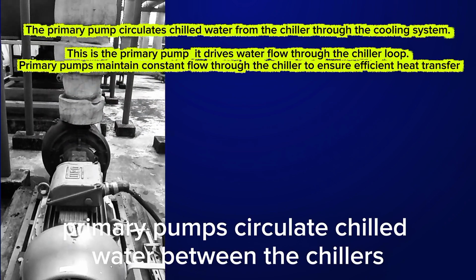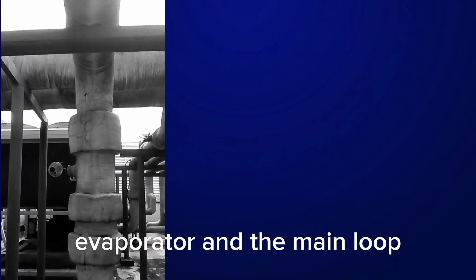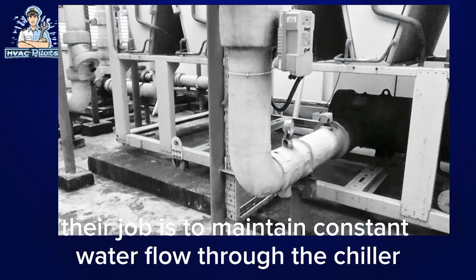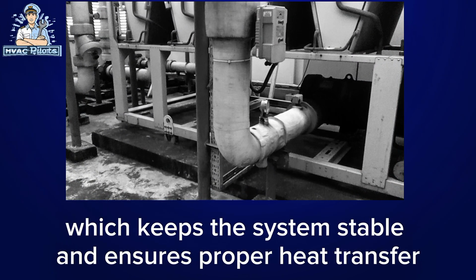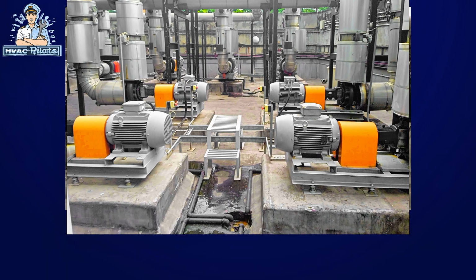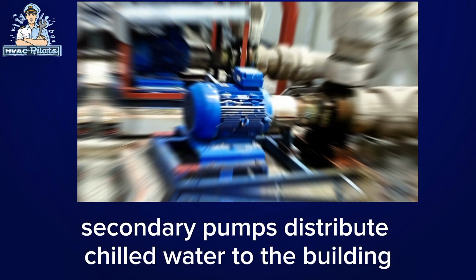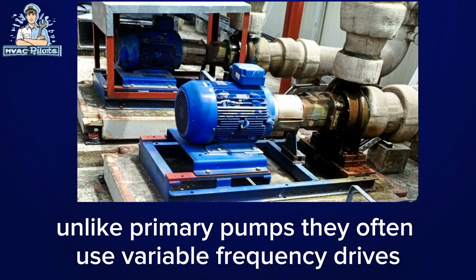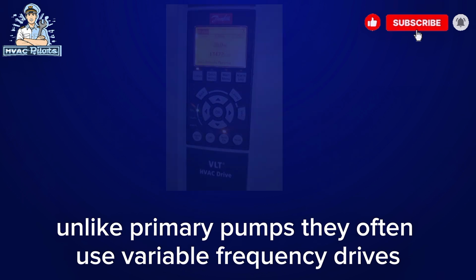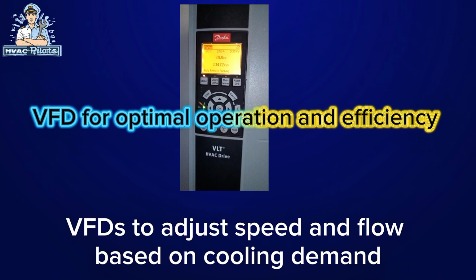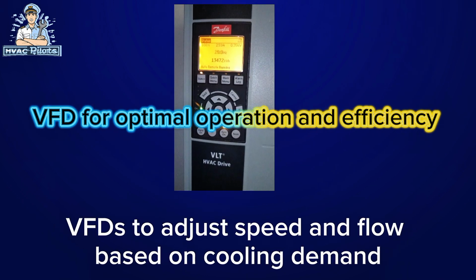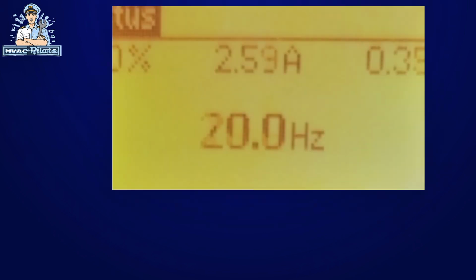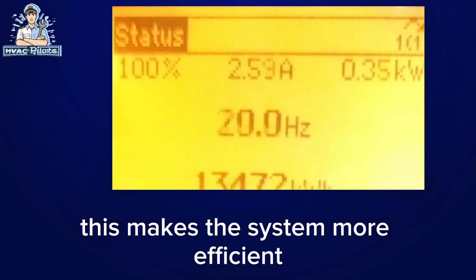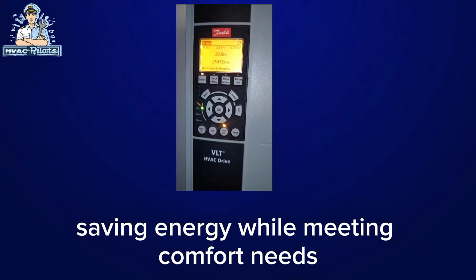Primary pumps circulate chilled water between the chiller's evaporator and the main loop. Their job is to maintain constant water flow through the chiller, which keeps the system stable and ensures proper heat transfer. Secondary pumps distribute chilled water to the building. Unlike primary pumps, they often use variable frequency drives, VFDs, to adjust speed and flow based on cooling demand. This makes the system more efficient, saving energy while meeting comfort needs.